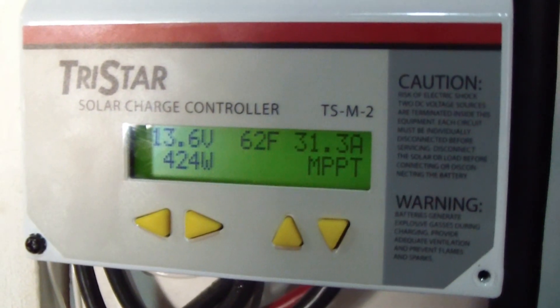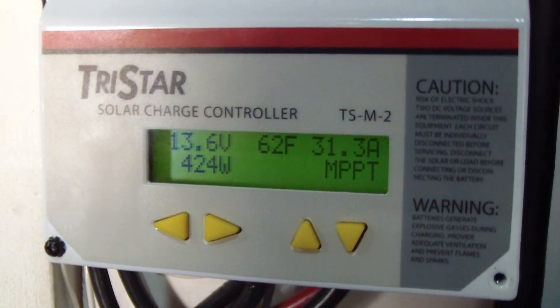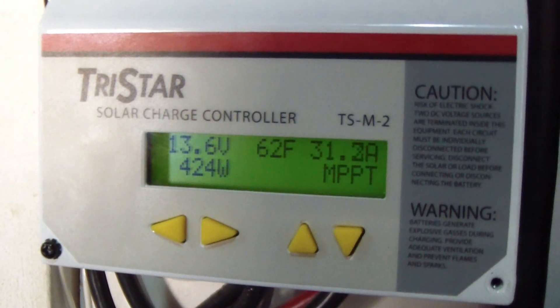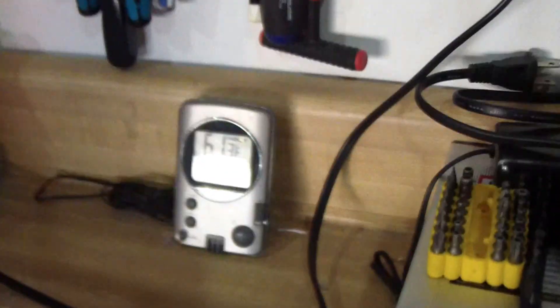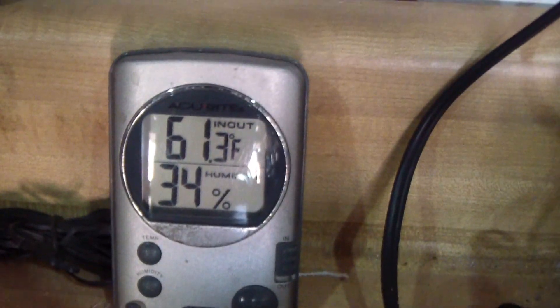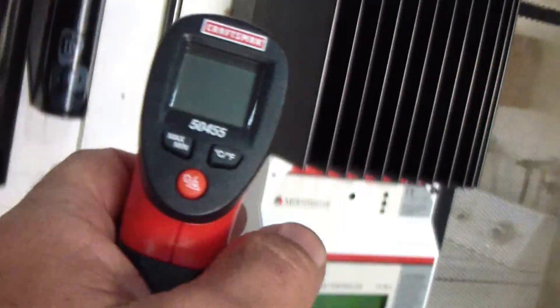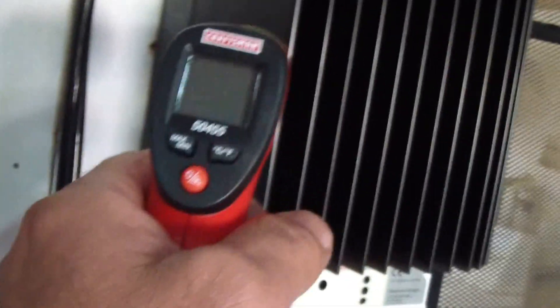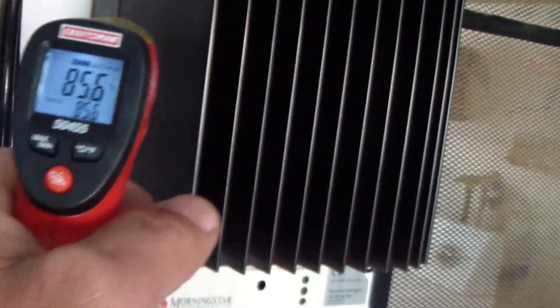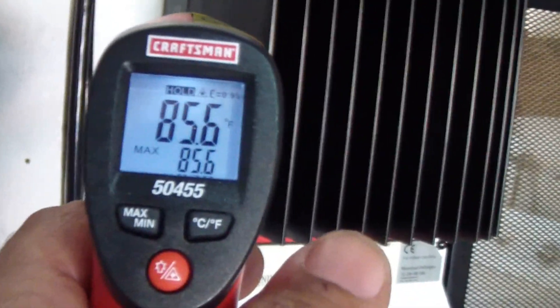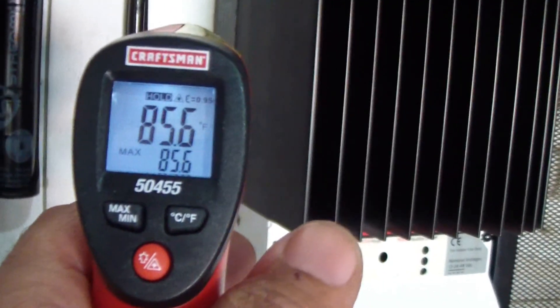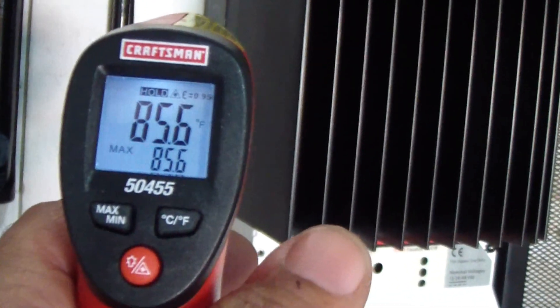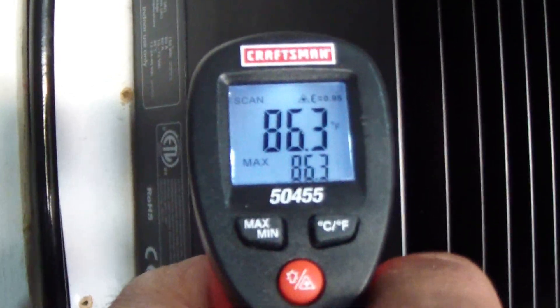The RTS temperature is 62 degrees Fahrenheit. Now it's 61 degrees here, so let's check the temperature with the infrared on the fins on the cooling heat sinks. About 85 degrees. Check it again. 86.